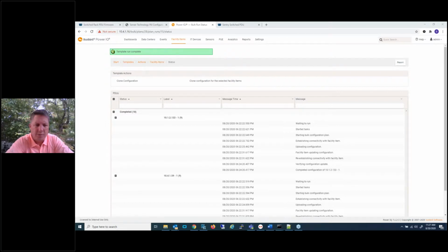And are there limitations with the startup stick? Well, the startup stick spreadsheet tool is only tailored to creating INI files on the startup stick that will configure the basics to bring it up on the network. But that's a good question, in that if you create your own INI files, you can put those files onto the startup stick and then use the startup stick to apply that INI file to the PDU. So that really is a fourth method.